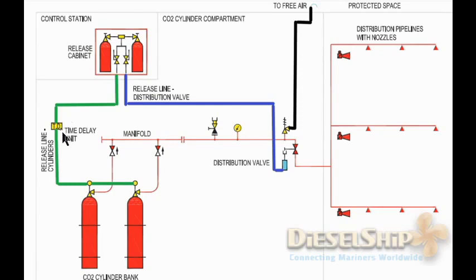The time delay unit can be either electrical or a simple empty bottle that creates a delay of 20 to 30 seconds — just the time needed to fill the bottle. The CO2 from the pilot bottle takes time to fill the empty bottle, and that is how the time delay is created. Electronically, there is a solenoid valve and a timer mechanism which, after the time delay of around 20 seconds, opens the solenoid so the CO2 goes and opens the main cylinder unit.